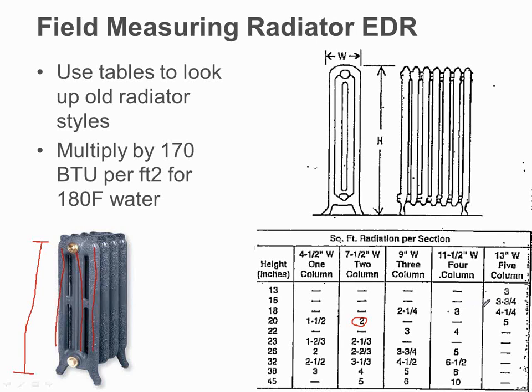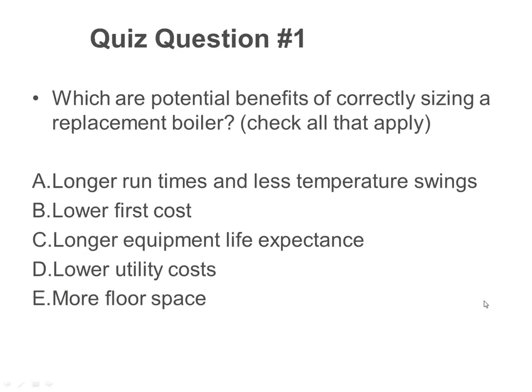So that's why we try to do this method. We're going to go around and count all these things up. Then we add up all the radiators or all the baseboard and sum them up, and that's the maximum amount your boiler could possibly shove in there. You couldn't possibly need a bigger boiler if you wanted to. So it's not uncommon that you'll go around a building and count up 80,000 BTUs of radiator and have a 200,000 BTU boiler. Where the hell are you going to send the other 120,000 BTUs? You have nowhere to send them.